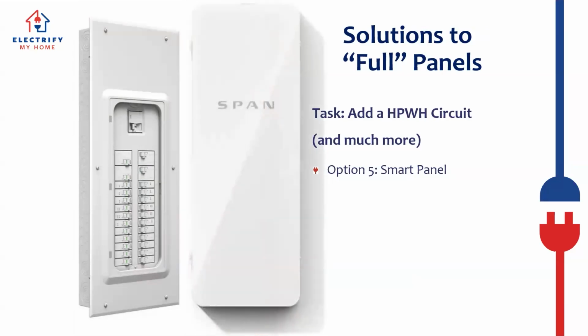Another great solution: adding smart panels. We've been doing more of these. There are several new options on the market - I'll mention the Span panel. The way this works is you can set a max capacity for the house. So if you have a max 100 amp feed, you tell Span your max is 100 amps, and anytime you start getting up towards that, it starts shutting off breakers in order - this breaker, then this one, then this one. The customer determines which loads to shed at any given time. They also get great feedback on energy use of all the breakers in the panel, and it can serve as a critical loads panel for a battery system as well, prioritizing which loads stay on or off.